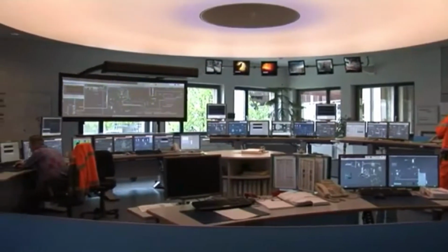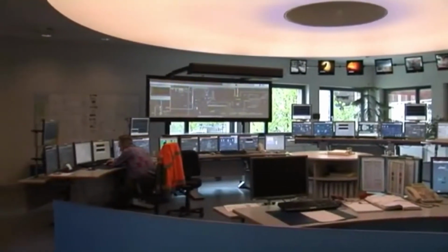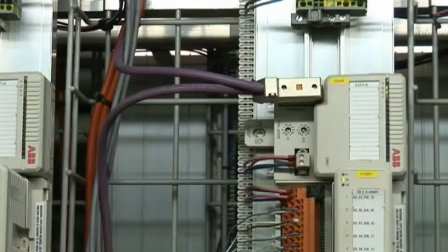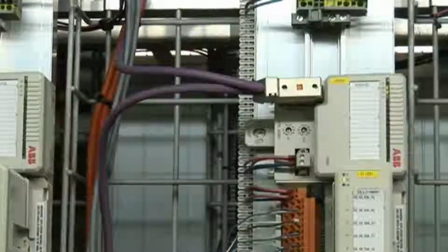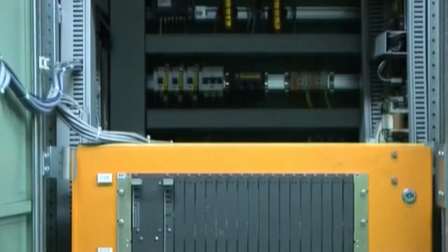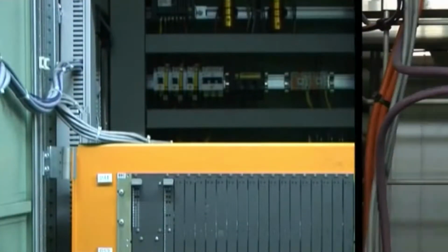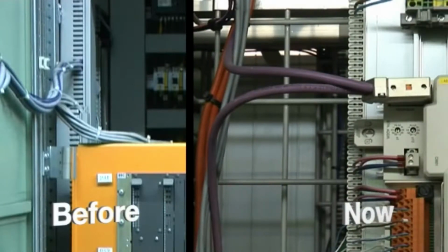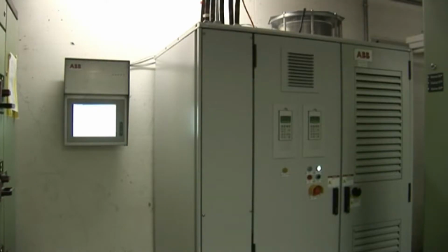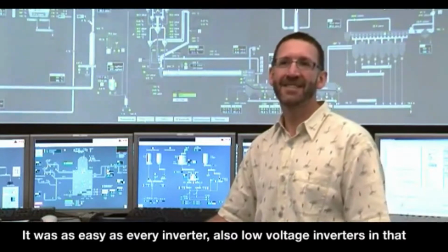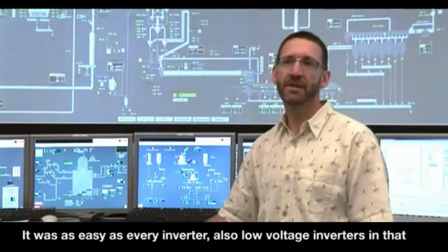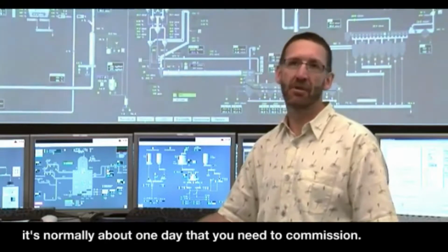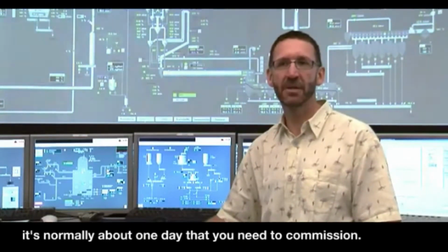The drive's interface with the new ABB 800XA control system is via Profibus, using a single cable shown here by the purple wiring, as opposed to many connections with the previous drive system. This is a big advantage during commissioning, as it takes minutes to commission a Profibus system compared to other systems. The simplicity of the installation and commissioning is also reflected in the reduced training time needed for end users. It was as easy as every inverter, also low voltage inverters. You know that it's normally about 1 day that you need to commission.